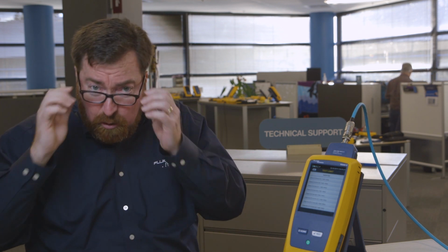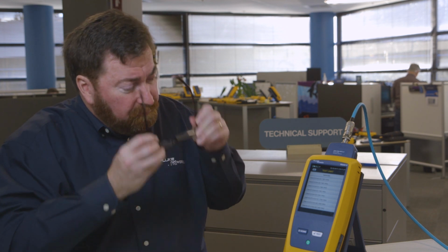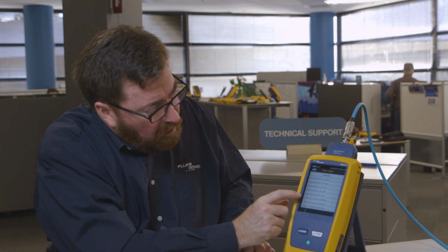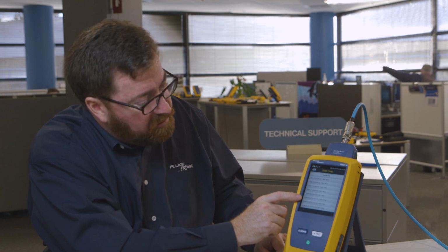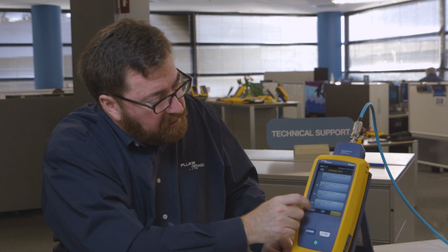Again, as we get into environments where there's more electromagnetic noise that may interfere with my cable, I'm going to apply stricter limits to the TCL value to make sure that the cable is properly balanced. That is, each leg of the pair is going to treat an external interference in the same way to be able to properly eliminate it. Let's choose our Class EA because we were testing 6A before, and we're going to use the E1 limits. I'll hit Save, Use Selected, and push Test to start.